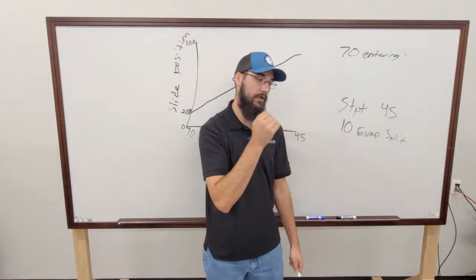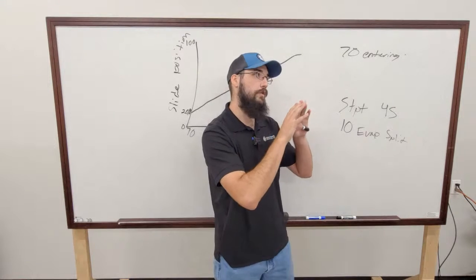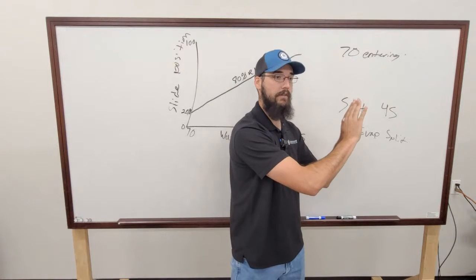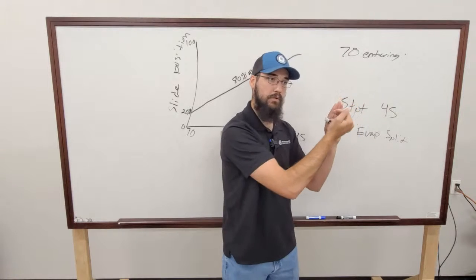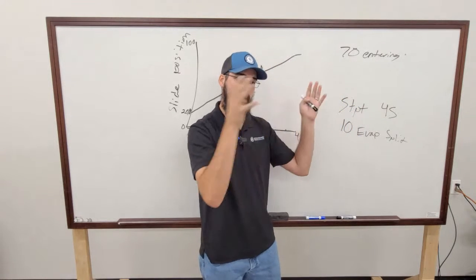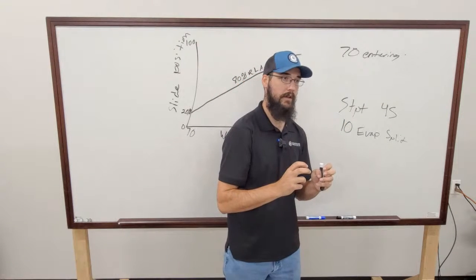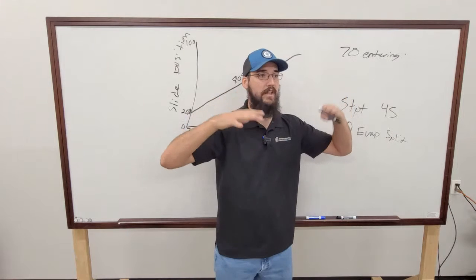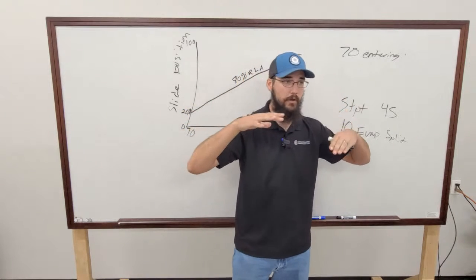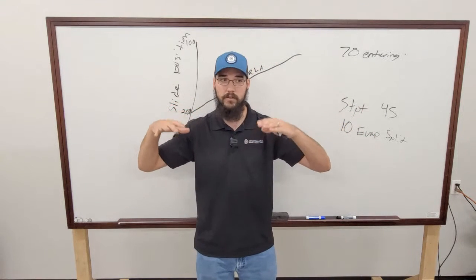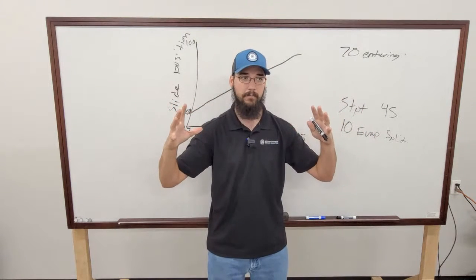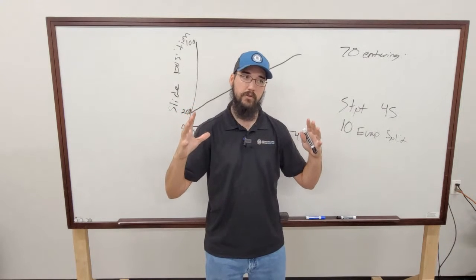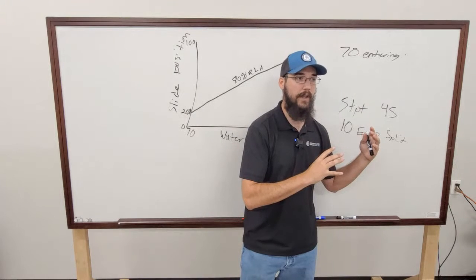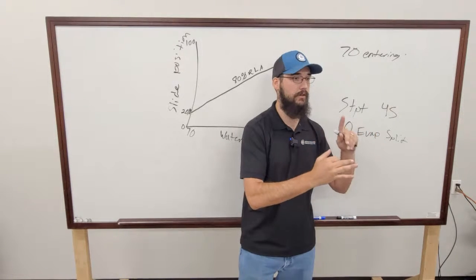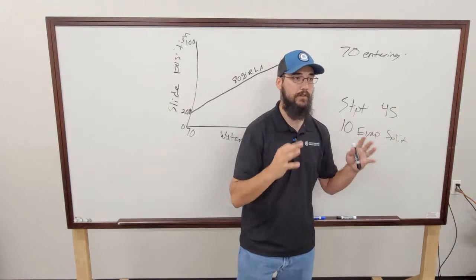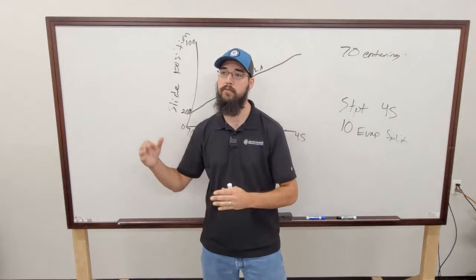But also you can push that system to run on the edge of its safety limits. And when you're in a pull down state and you're outside of normal design parameters, the system is very unstable. The refrigerant pressures are unstable, the loading is unstable, the water temperatures are unstable, and there's a lot of fluctuations happening. And what that'll lead to is you'll nuisance trip trying to pull down, whether it be high pressure, low pressure, current limit, whatever it is, you'll start to have nuisance trips on circuits before they ever get the loop fully pulled down.